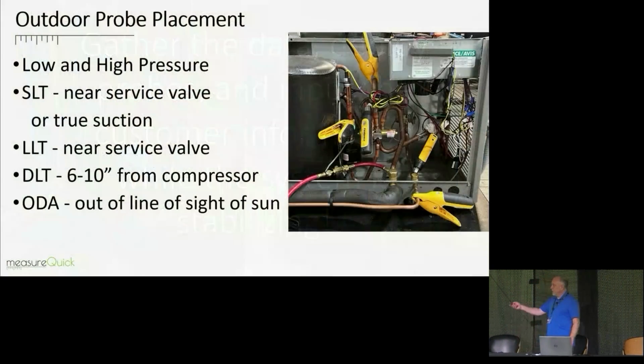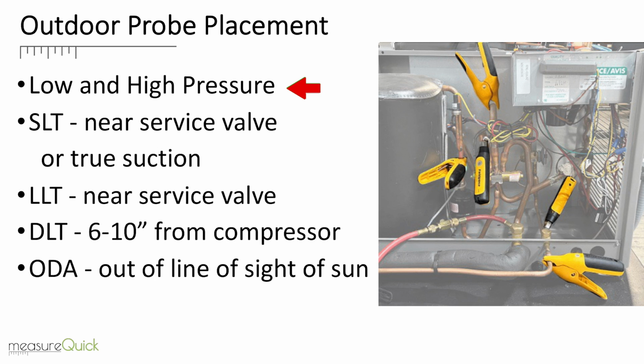So while we're letting that system stabilize, we're going to start getting the information off that and putting it into the system. Low and high pressure near the service valves, or true suction, liquid line, near the service valve. Discharge line is optional, 6 to 10 inches. Outdoor air, we want to be out of line of sight of the sun here, so you can sort of see where we got the probes placed. Pretty typical of what you guys would be doing on any system that you'd be working on.